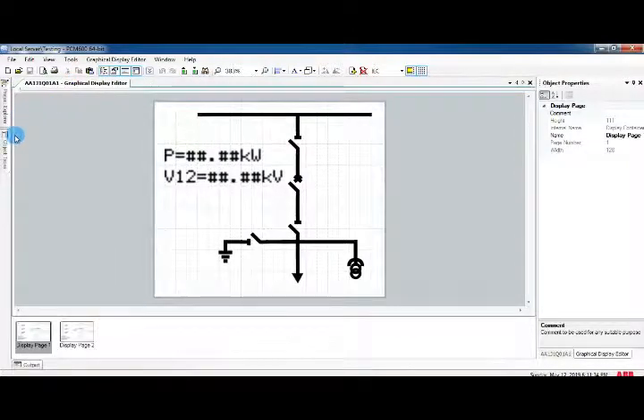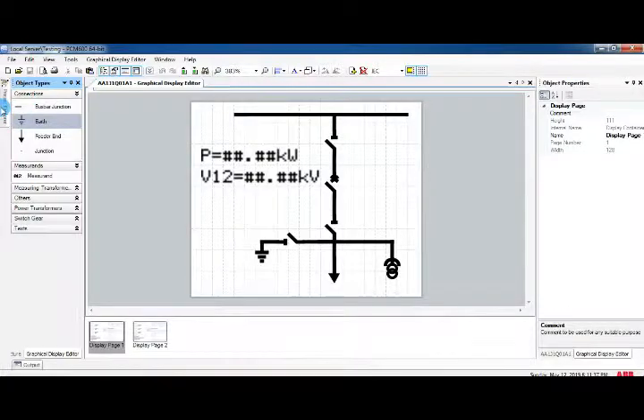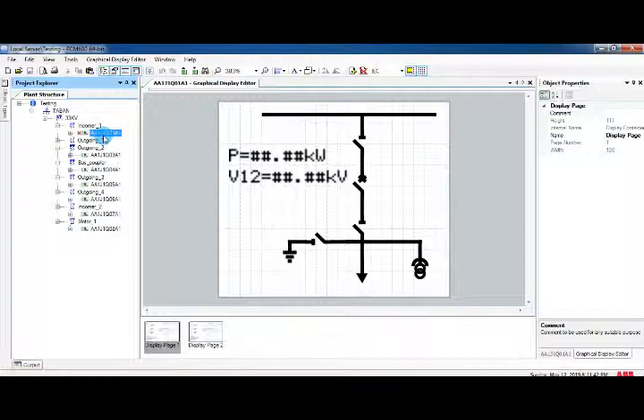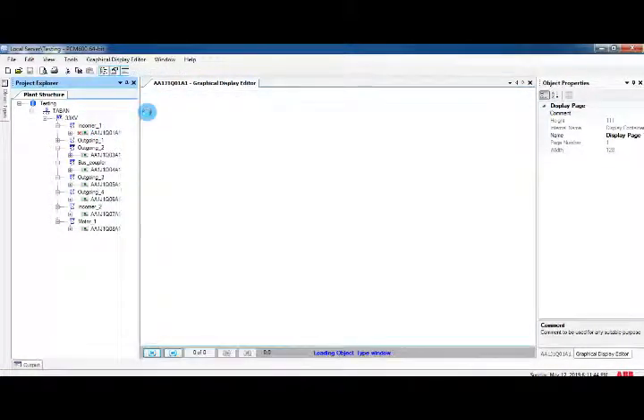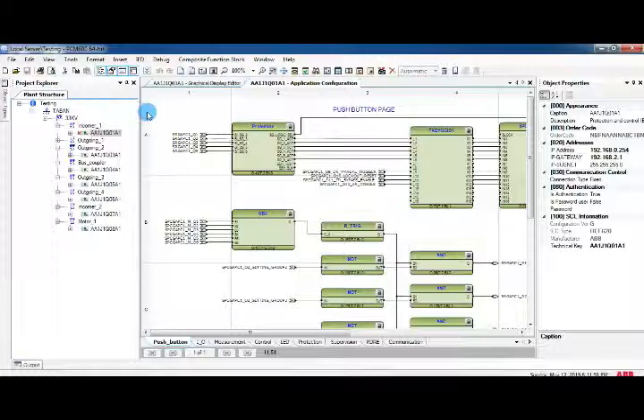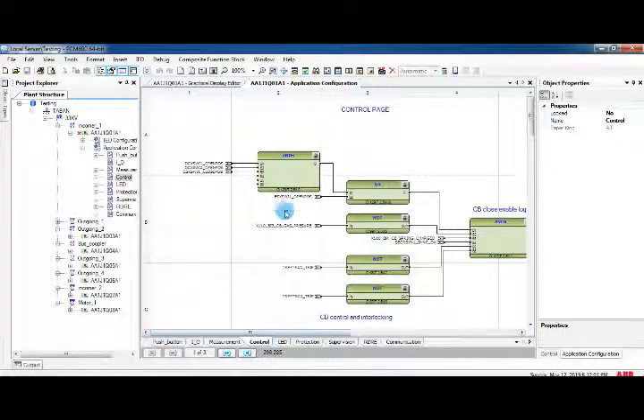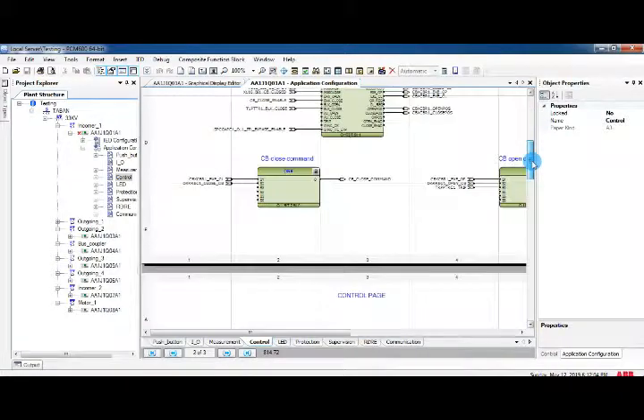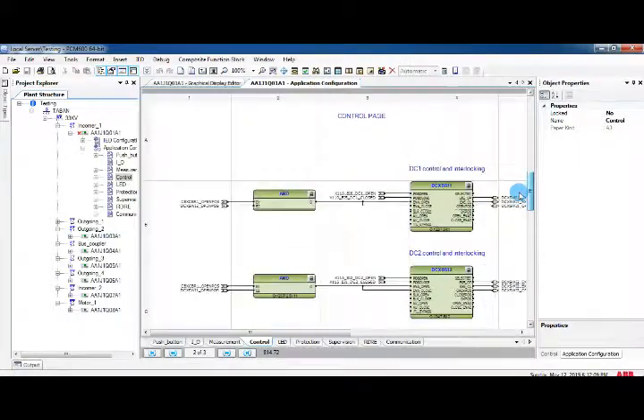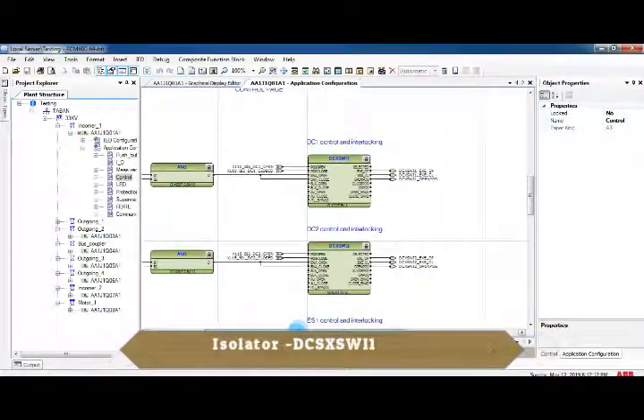Once done, just save this drawing and you can directly write it to the relay. This display will work when the block in the application configuration has open and close indication status inputs assigned properly. Ensure that all equipment has corresponding open and close status inputs, and you can verify by giving the corresponding input — your mimic will work accordingly.